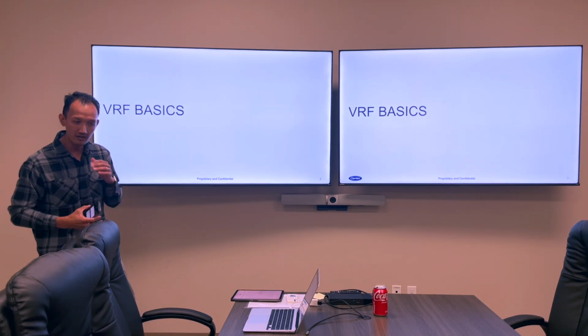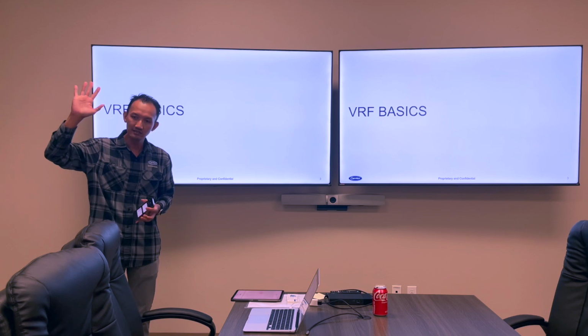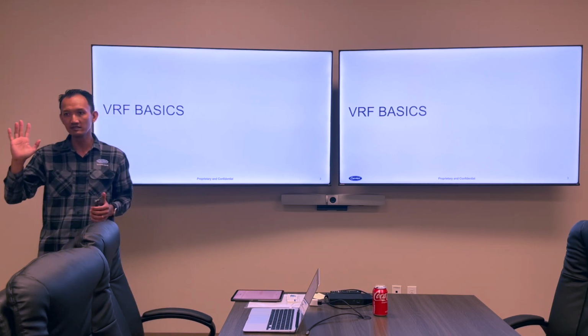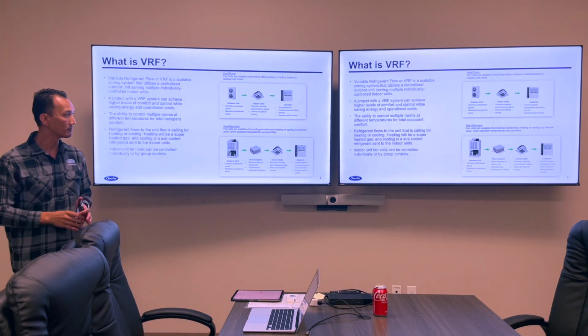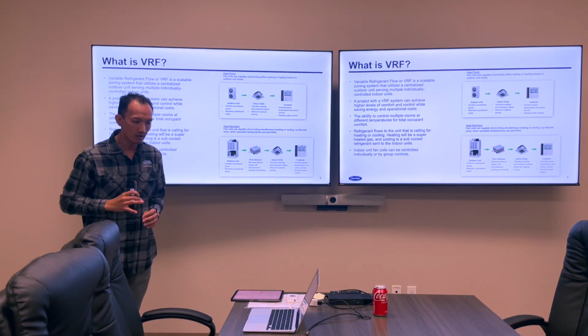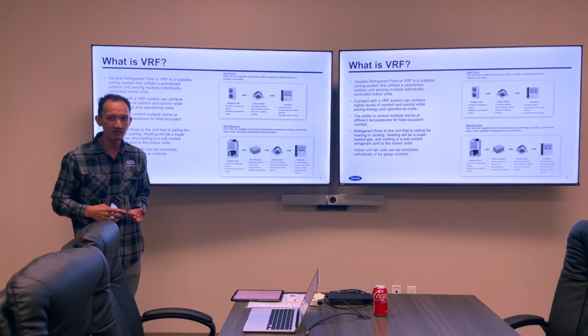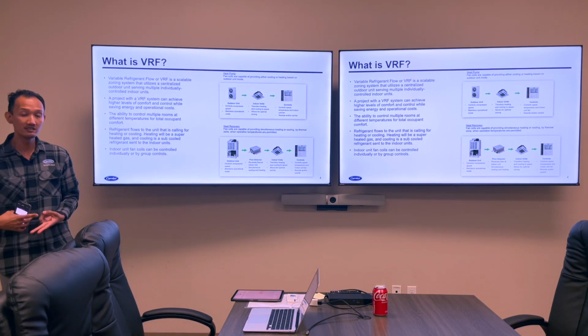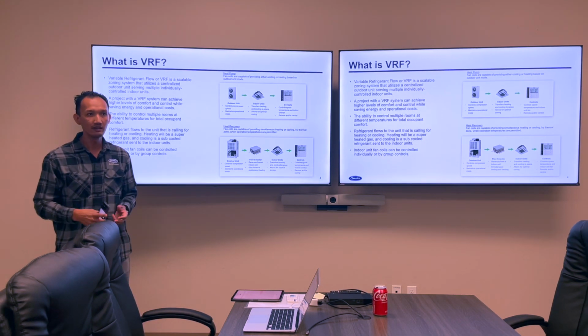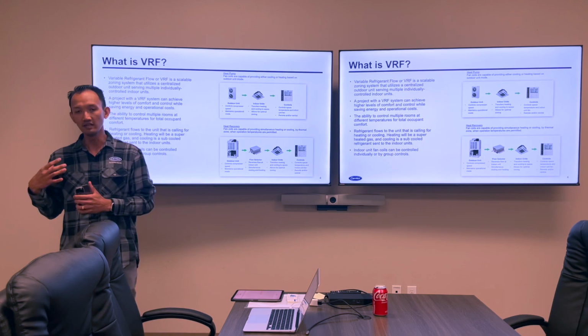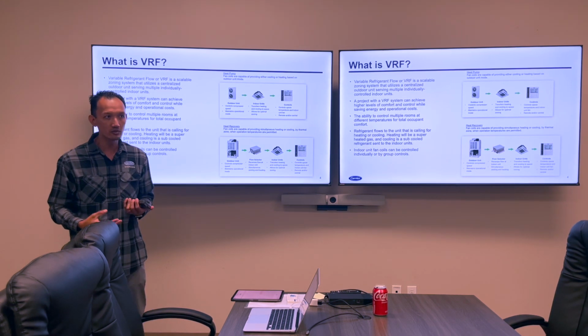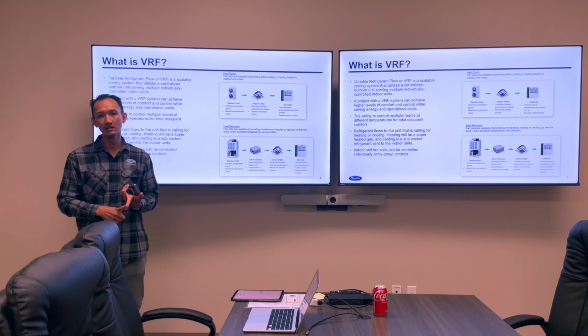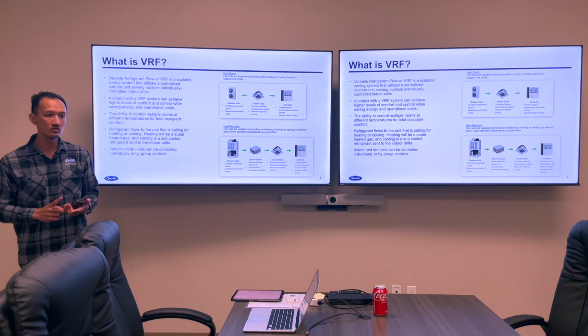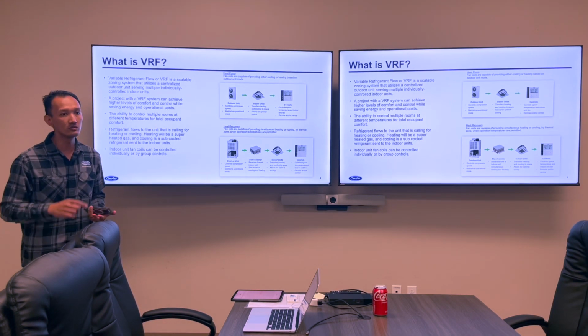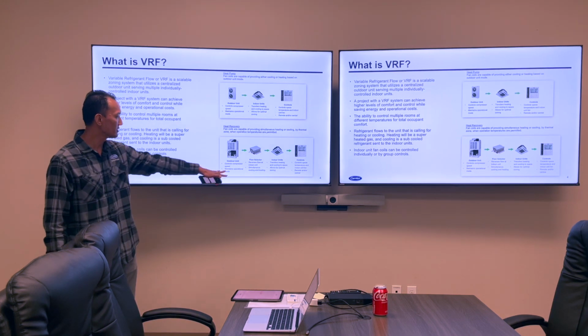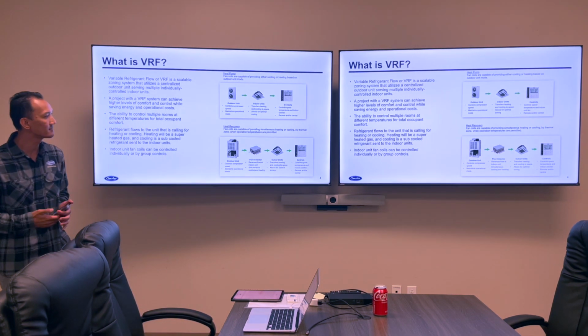But first, VRF basics. I take it everybody has heard of VRF, knows what it is generally. But for those who aren't quite as familiar, just real quick, VRF stands for variable refrigerant flow. It's basically a heat pump, right? It's got an outdoor unit and an indoor unit. The thing that makes it special is that you can connect multiple fan coils to one outdoor unit. You can do long line lengths. You can do simultaneous heating and cooling with the introduction of a flow selector box.